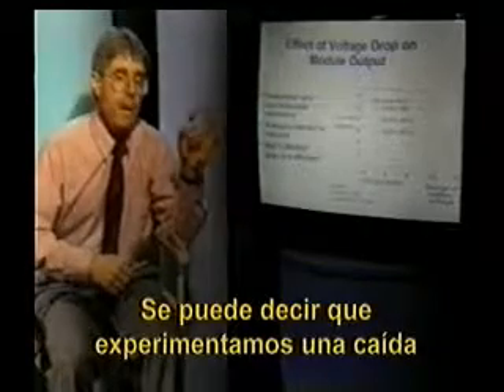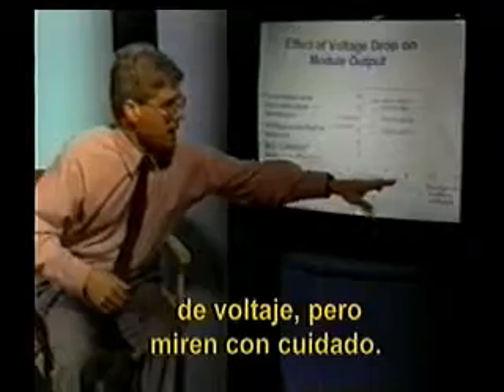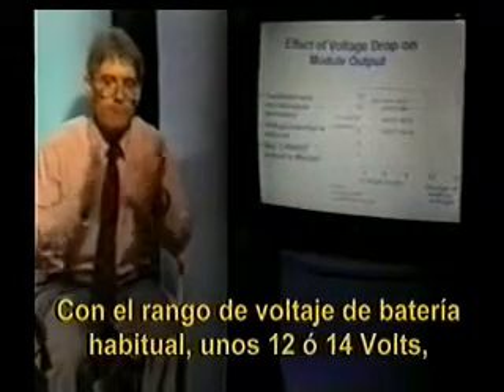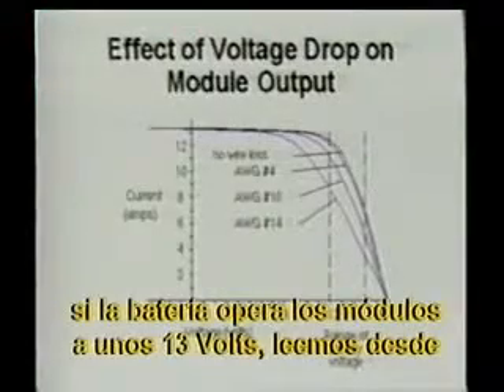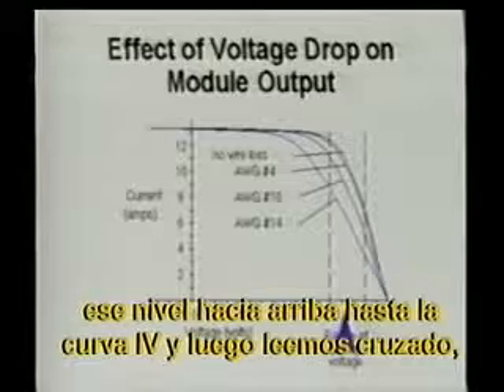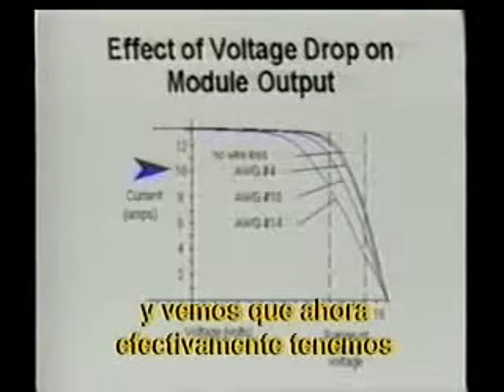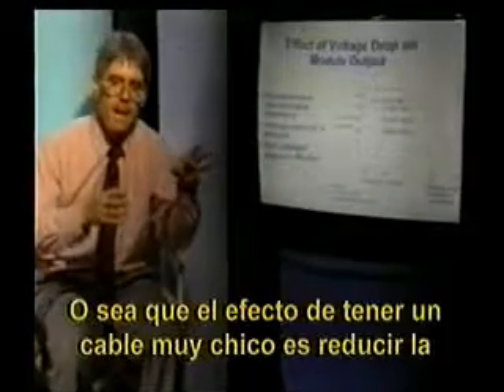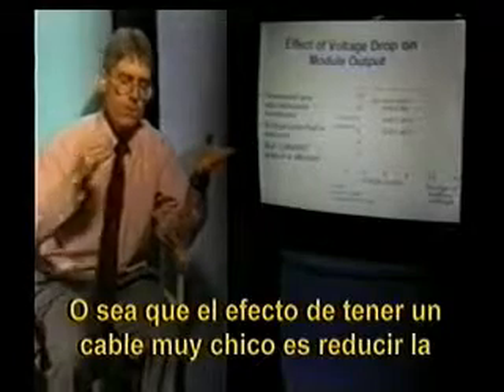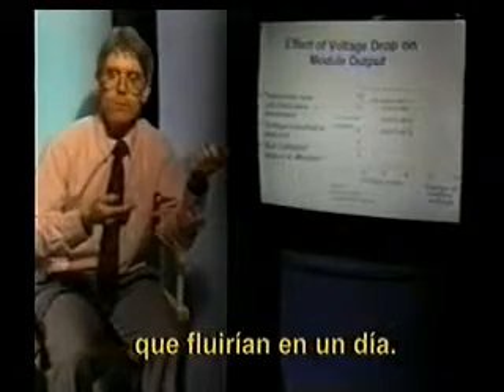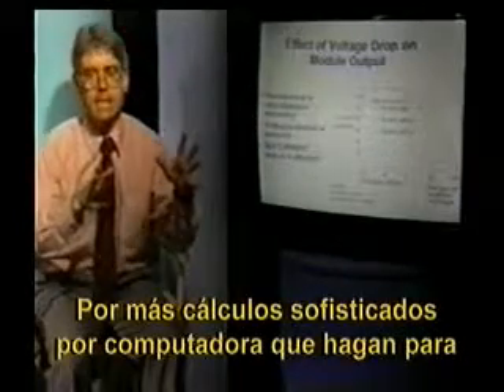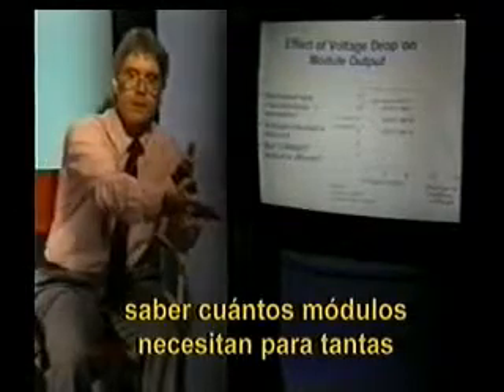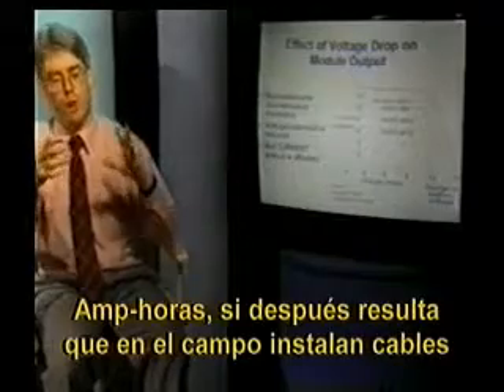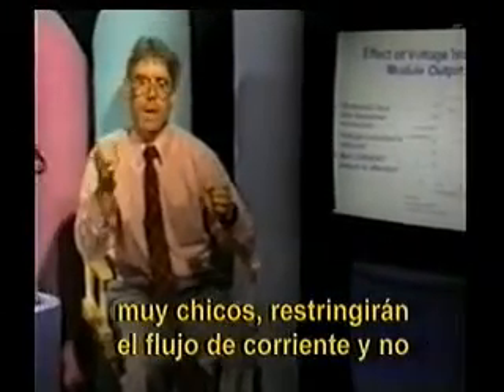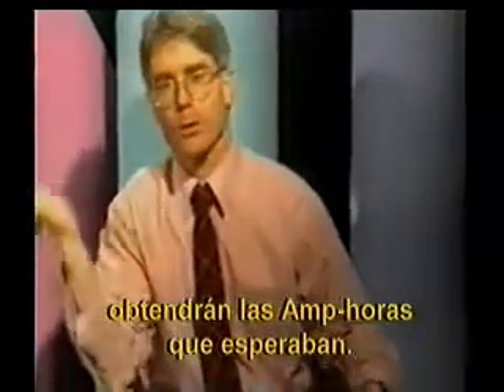Now, you'd say, well, you're experiencing a voltage drop. But look carefully. If we look at the range of battery voltage that we typically deal with, somewhere around 12 to 14 or so volts, if our battery is operating our modules, let's say at roughly 13 volts or so, we read up from that level to the IV curve and then read across to find that effectively we now have lower current flowing. So the effect of having too small of wire is to reduce the amount of current, or the amount of amp hours in a day, that would flow. You could have gone through all of your fancy computer-based sizing to calculate the number of modules you need to deliver your amp hours. And then if in the field you install wires that are too small, you're going to restrict that current flow, and you will not get the amp hours delivered that you predicted in your fancy computer printout.